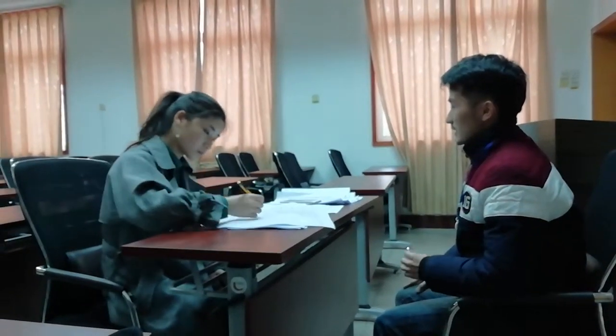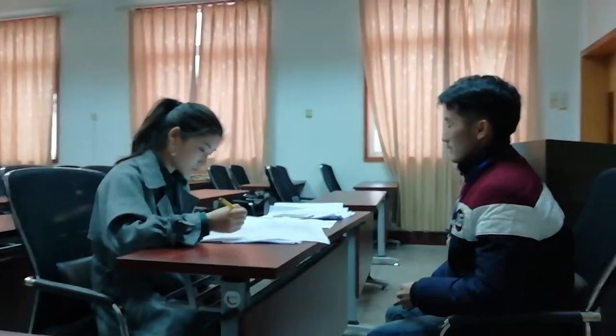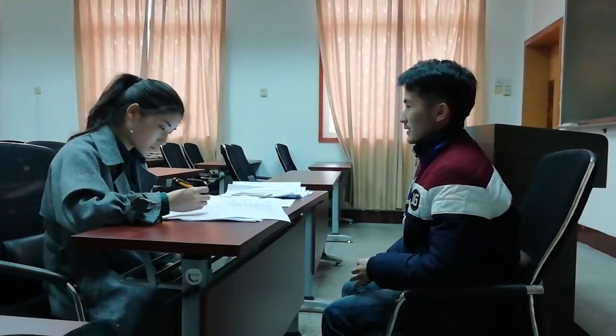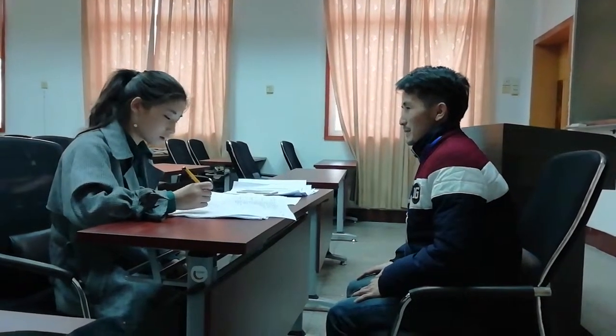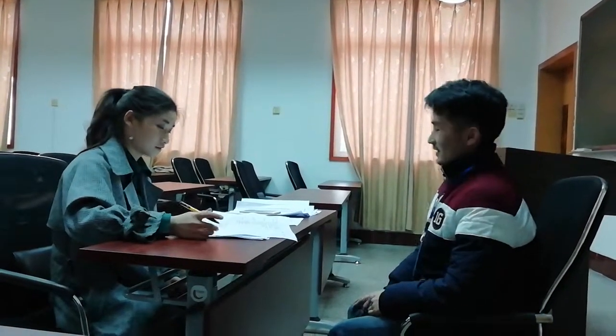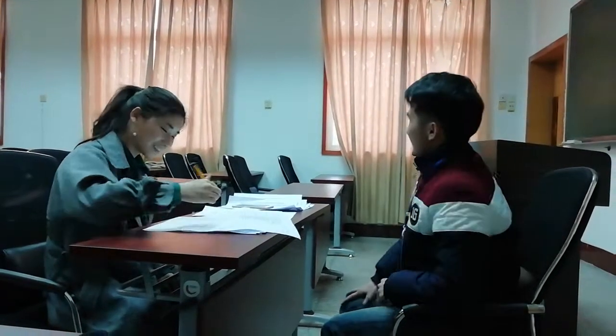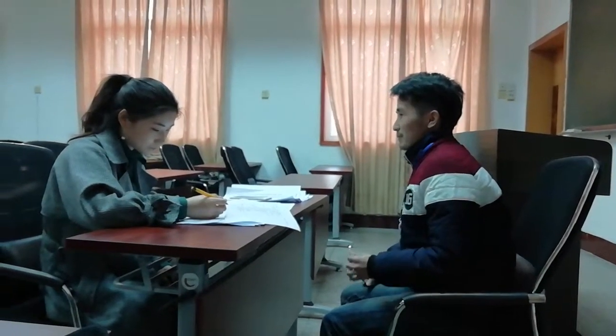5. Contact resistance. 6. Measure the CB opening and closing time, measuring the fixed opening and closing time of CB, and whether the contacts close and open together or not. 7. Measure the speed of CB opening and closing.